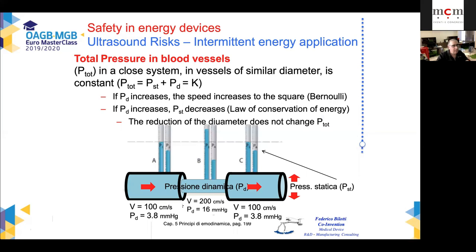We're getting close to the end. One surgeon during a presentation described to me how important it was to compress the vessel repeatedly, applying electrical energy or ultrasound energy indiscriminately. So either one was not important, but zapping repeatedly the vessels to reduce the size, because the reduction of its size reduced the pressure that the vessel will leak at. Extremely wrong, because the pressure inside the vessel is the addition of two pressures, a dynamic and a static pressure. By reducing the size, you, yes, reduce the static pressure, but you increase the dynamic pressure. So the addition of the two is always the same. And it's just remembering what you do to water the garden. You squeeze the hose with your thumb, and the pressure increases, but the static pressure decreases on the vessel.